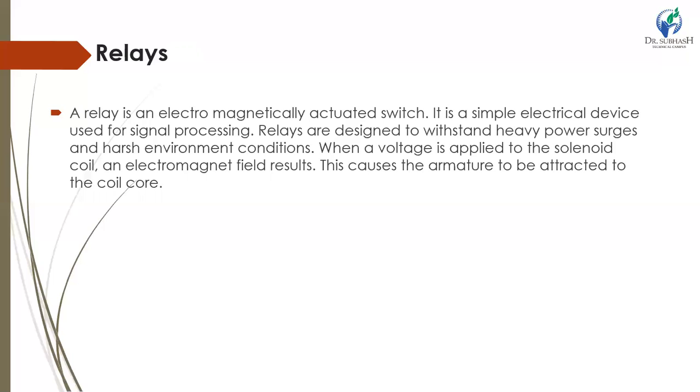A large number of contacts can be operated by an appropriate relay, in contrast to the case of the push button station. Relays are usually designated as K1, K2, K3, etc. Relays also possess interlocking capacity as a safety feature in control circuits. Interlocking avoids simultaneous switching of controls.